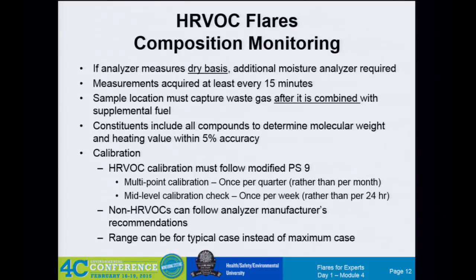Even the once per quarter, three-point multi-point calibration, once per quarter, not once a month, has to be done in triplicate. The really interesting one is that mid-level calibration, once per week. That's a triplicate run, one time a week. So if you're ordering an analyzer from somebody, the guys at Yokogawa or Siemens or somebody who's doing the GC work for you, their data management system, their DAS, is probably designed for a daily cal, not one in triplicate in the middle of the week, right? So all these little data capture things we just have to be aware of, and you have to do both.